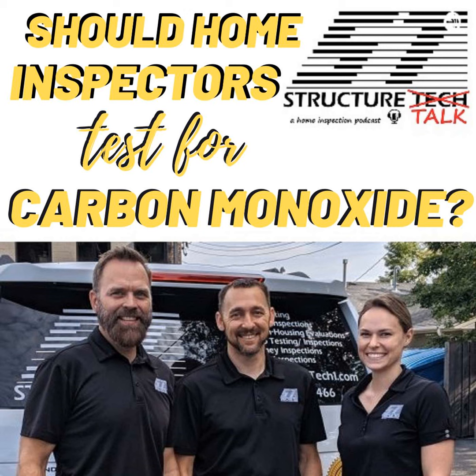And we actually got our hands on the CO testing standards for the gas company here in the Twin Cities, or one of them, Centerpoint Energy. We've got their little cheat sheet that they give to their techs, and their threshold is 100 parts per million. When it's above that, they yellow tag the furnace and say it should be serviced. So we pretty much follow suit. If it's above 100 parts per million, we recommend having the furnace serviced.